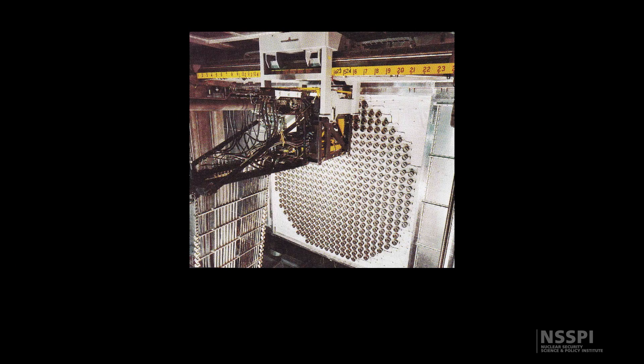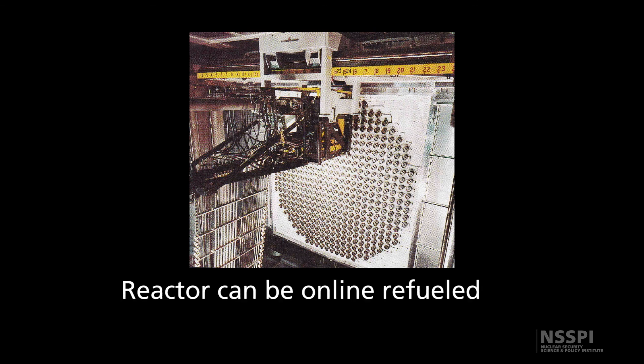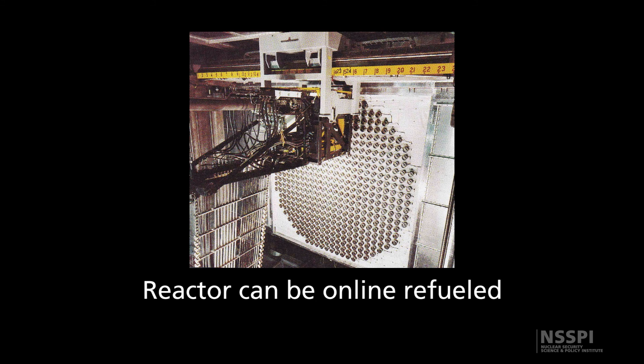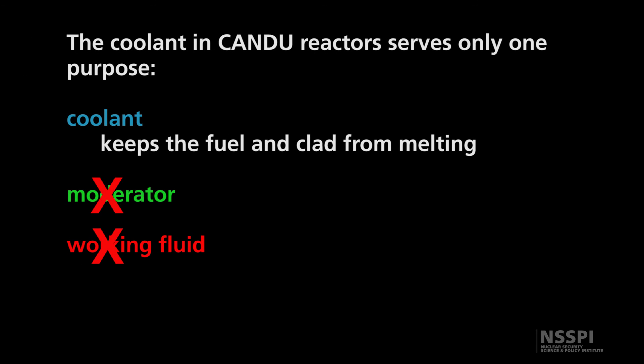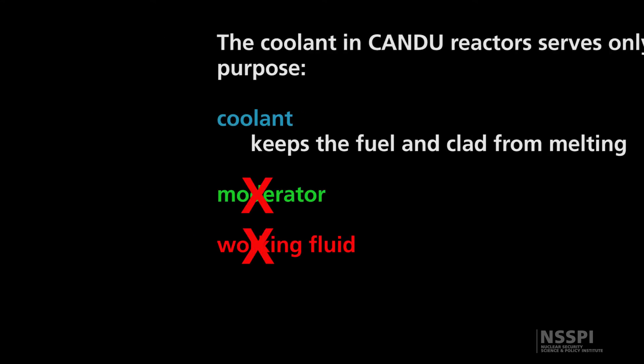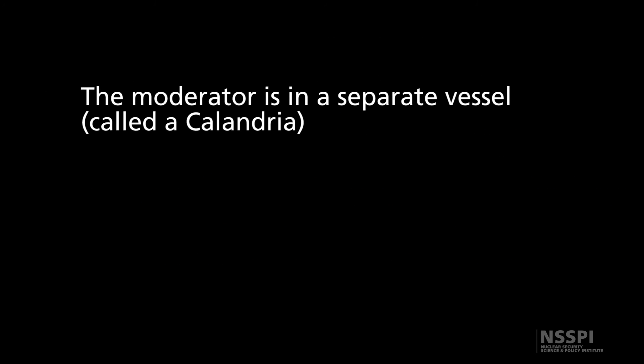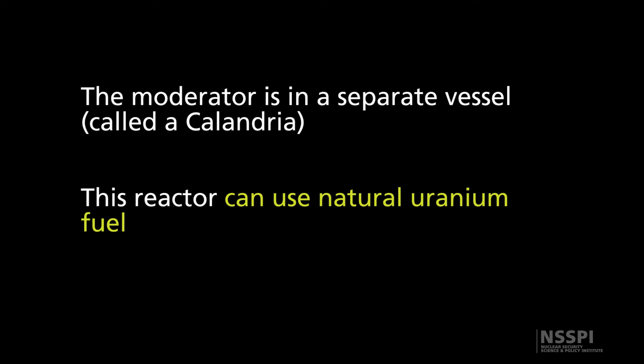One of the CANDU reactor's more interesting characteristics is that it can be online refueled — while the reactor is still operating, individual pressure tubes can be shut off, fuel pulled out, and new fuel inserted. The coolant here only serves the purpose of keeping the fuel and cladding from melting. The moderator, which is the heavy water in a separate vessel called the Calandria, moderates the neutrons. Since it has a heavy water moderator, it can use natural uranium fuel, because heavy water absorbs far fewer neutrons than light water, so the fuel does not need to be enriched.